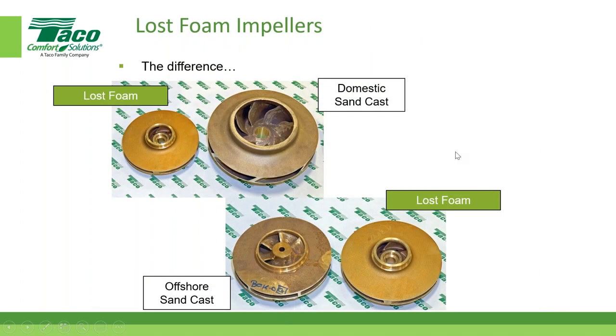Let's talk about our impellers, okay? Obviously that's a very important part of an FI, CI pump or any pump, right? And Rich reminds me that besides the shaft, it's really the only moving component of these pumps. The water moves through there, but it's the impeller that's spinning. So at Taco, for our pumps, at least the FI, KV, TA, CI, KS, the majority of them, we use the lost foam process to manufacture our impellers. We're very, very proud of that. It really has helped our efficiencies and the quality of our impellers.